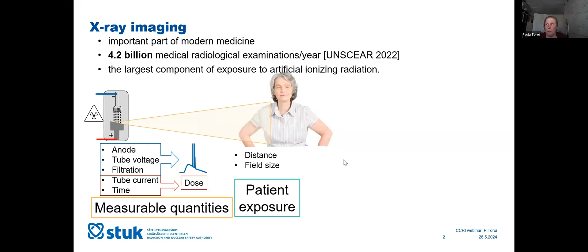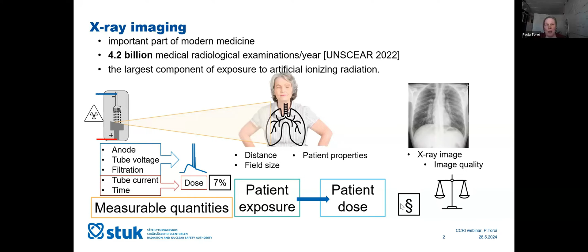Then with this setup, we will get the X-ray image with some specific image quality. When we want to do optimization between the image quality and the patient dose, we normally aim for something like a 7% uncertainty with k equals 2. This is set in the IAEA TRS-457 as a good target uncertainty for our dose measurements or air kerma measurements. Also, because radiation has detrimental effects, we need legislation and requirements for dosimetry measurements. So when we replace the patient with our dosimeter, we can do the dose measurements.